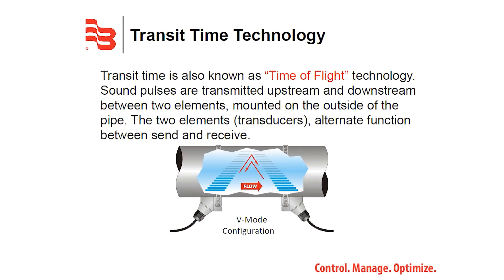Ultrasonic sound is sent using pulses in both directions of flow. A popular analogy is to think of a canoeist going from one side of the river to the other — as he goes with the current, he gets to the other side much quicker than on the return path. Ultrasound does the exact same thing. What is being measured is the time it takes for sound transmission in both directions; that differential in time tells us the velocity of the flow.